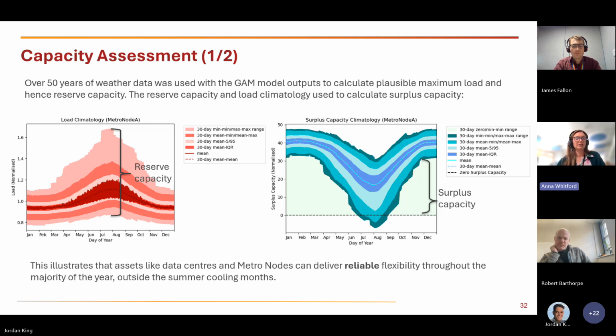We showed through the analysis that the larger sites — the data centres and metro nodes — were capable of providing reliable flexibility throughout most of the year, outside of the much warmer summer months when the reserve capacity is needed for cooling. Outside of that, the reserve capacity is actually surplus and could be used for flexibility.